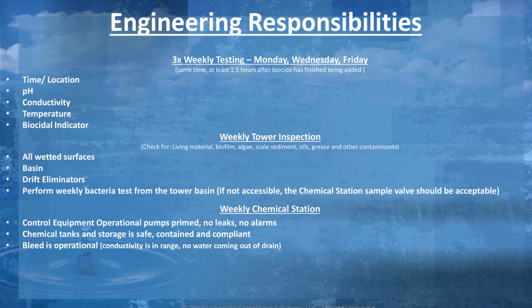Second, the responsible person will be inspecting the system for living material, biofilm, algae, scale, sediment, oils, greases, and other contamination on a weekly basis. When you are inspecting the tower, look at all the wetted surfaces. This would be everything from the basin to the fill to the distribution on the top of the tower. If you find any evidence of living or dead material, you must record it on your weekly log sheet in Section 3 of your logbook.